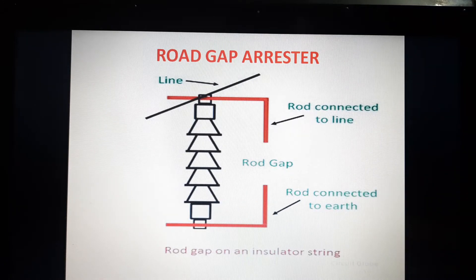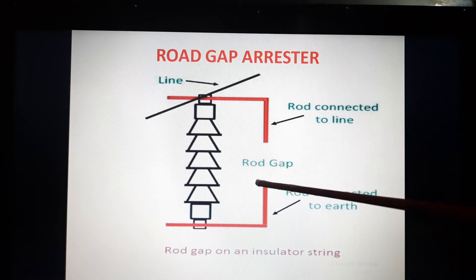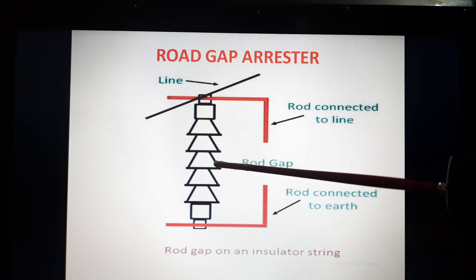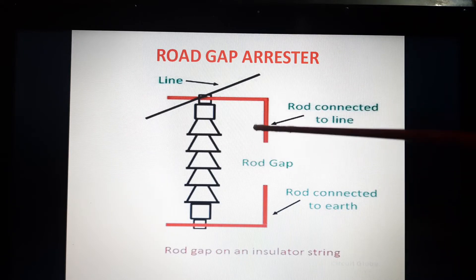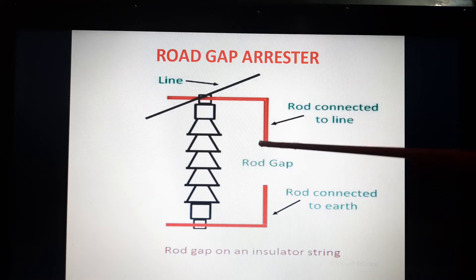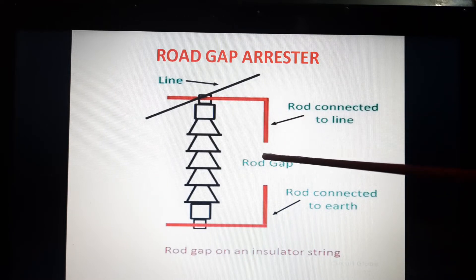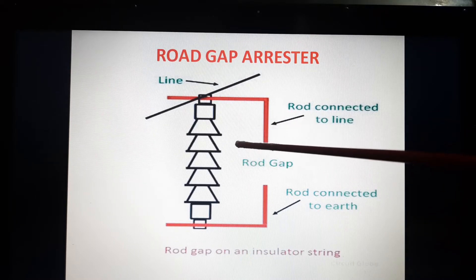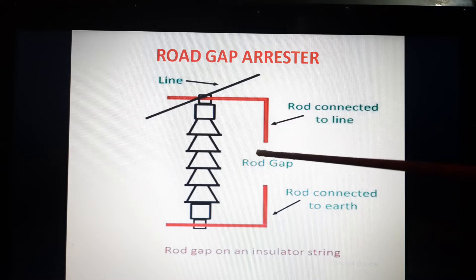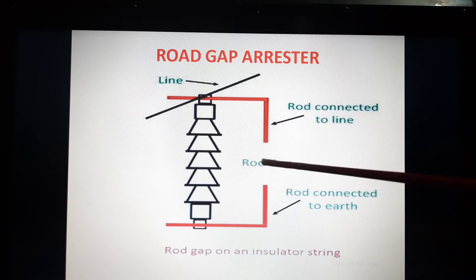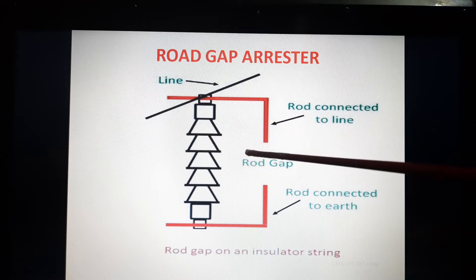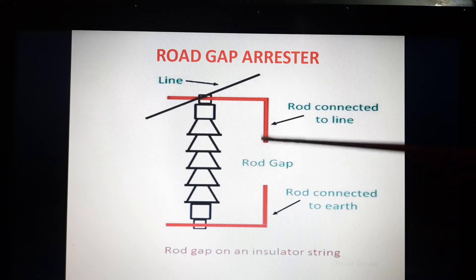One thing we have to be very clear: the distance between the gap and the insulator must not be less than one third of the gap length. Otherwise, the arc may reach and damage the insulator. So we have to keep this distance greater than one third of the gap length.